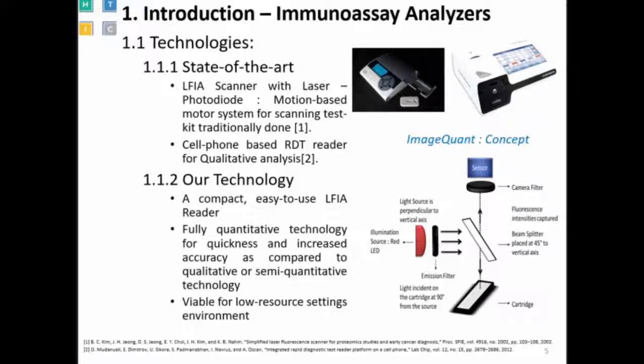For quantitative measurement, we have developed an instrument. State-of-the-art instruments use a photodiode and laser for sensing. In our technology, we use an imaging machine vision camera for capturing the entire cartridge, which captures test and control lines. The control line is always present if the test is valid. The test line will be present or absent based on yes or no, whereas in quantitative measurement the test line intensity varies proportionally or inversely proportionally with the test concentration.